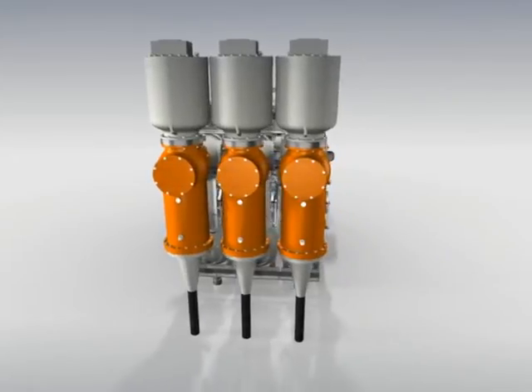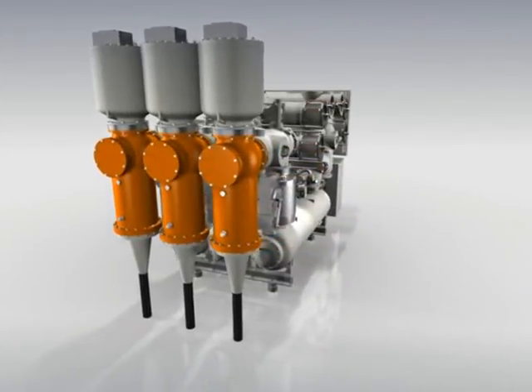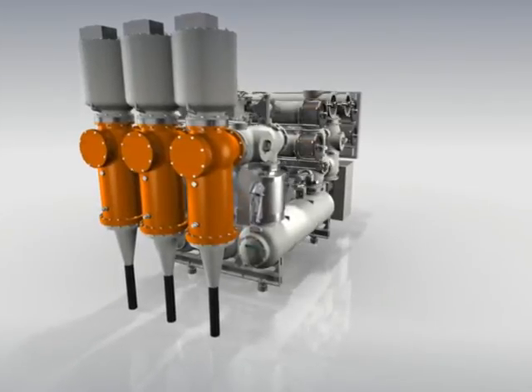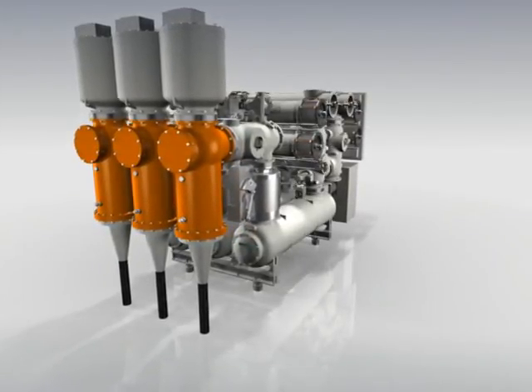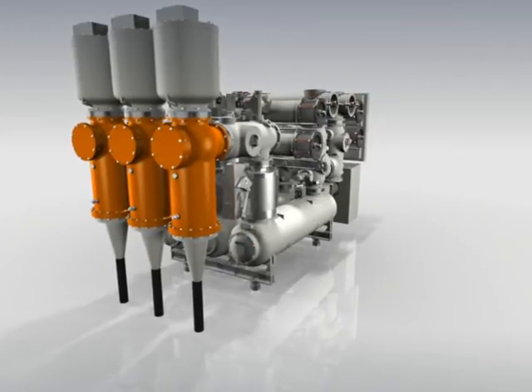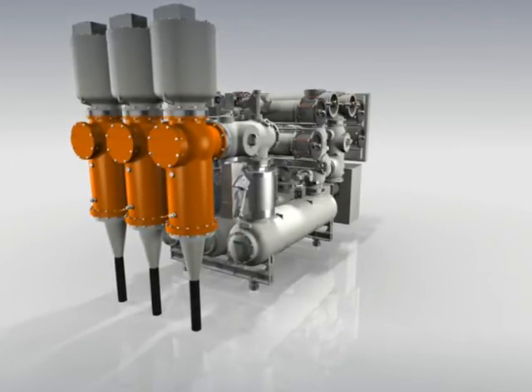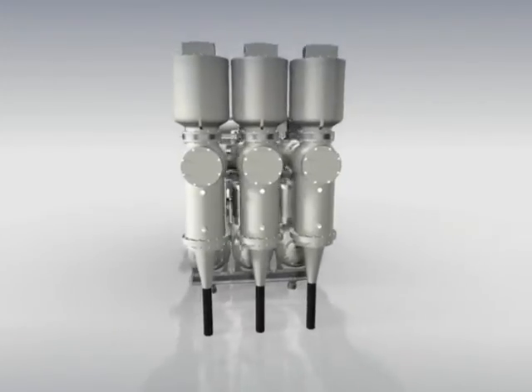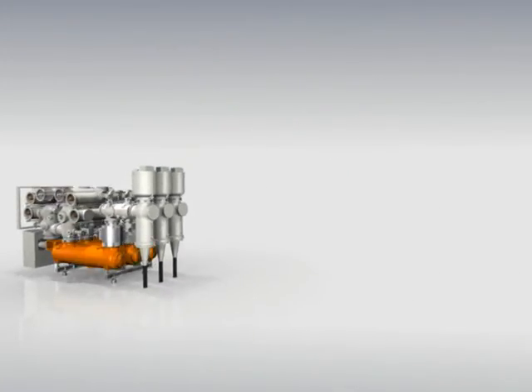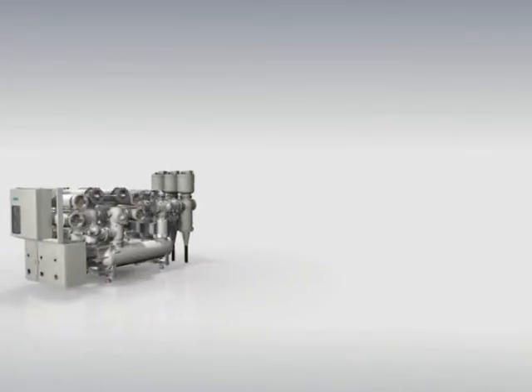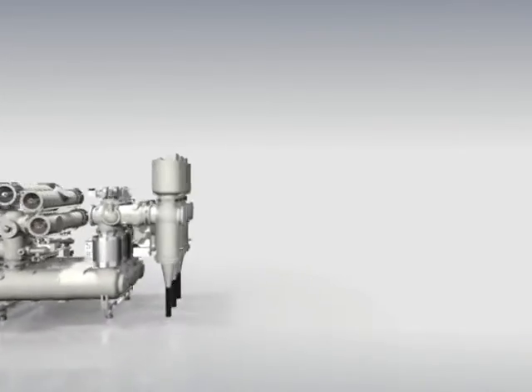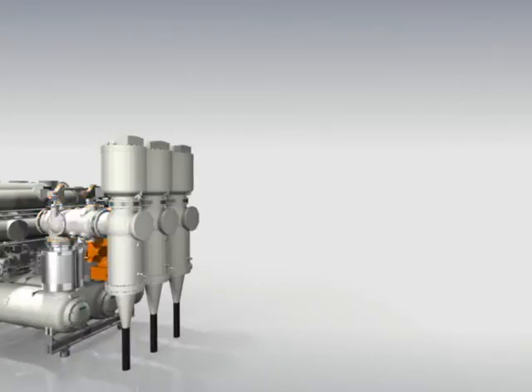The cable termination module links the gas-insulated switchgear with a high-voltage cable. This module is the transition point from the sulfur hexafluoride gas insulation to other insulation media. It can be fitted with a conventionally fixed cable connection or with a modern dry plug-in cable connection. To provide for maximum versatility, a number of additional connecting and termination modules are available.